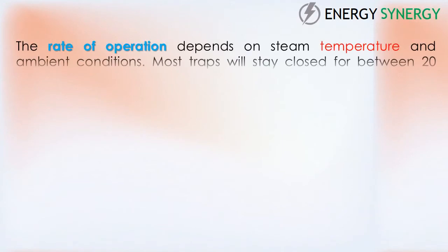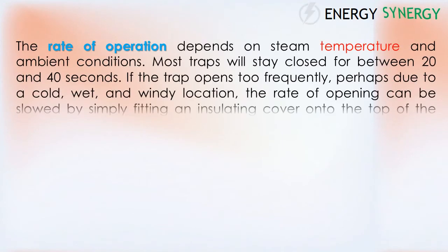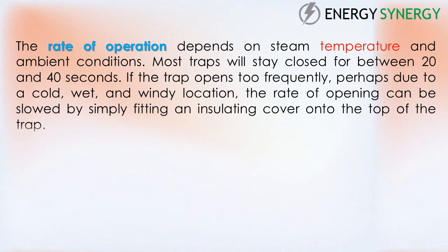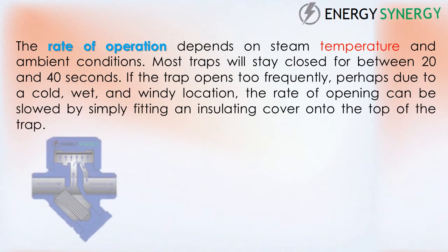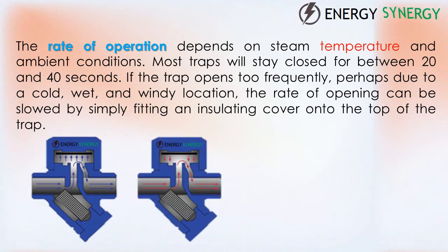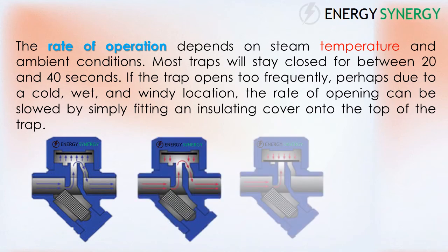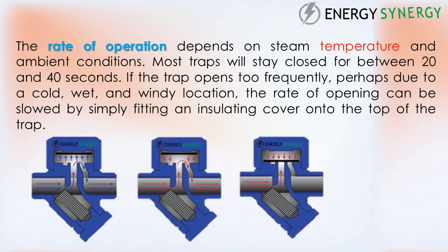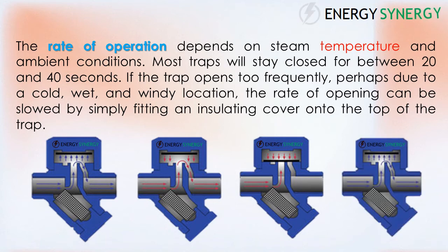The rate of operation depends on steam temperature and ambient conditions. Most traps will stay closed for between 20 and 40 seconds. If the trap opens too frequently — perhaps due to a cold, wet, and windy location — the rate of opening can be slowed by simply fitting an insulating cover onto the top of the trap.